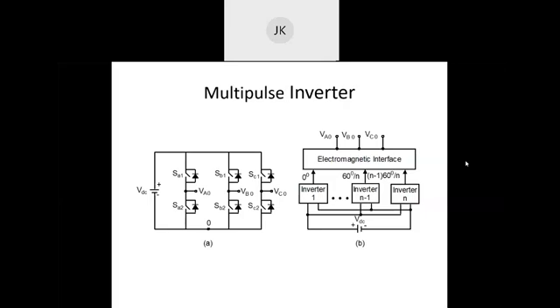This is done using a zigzag transformer, where we connect these single pulse 6-pulse inverter units with a particular phase angle. If we keep 0 degree phase difference, it will produce the same output with only height increasing. So by combining using this zigzag type transformer, we can get a multipulse output.